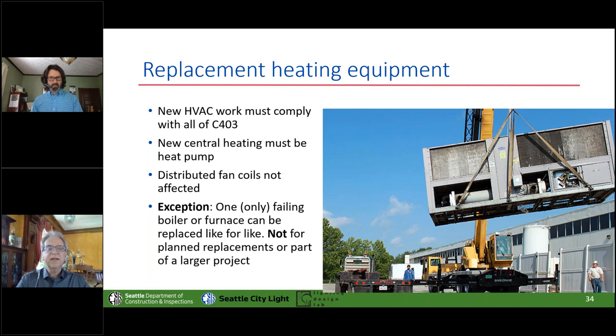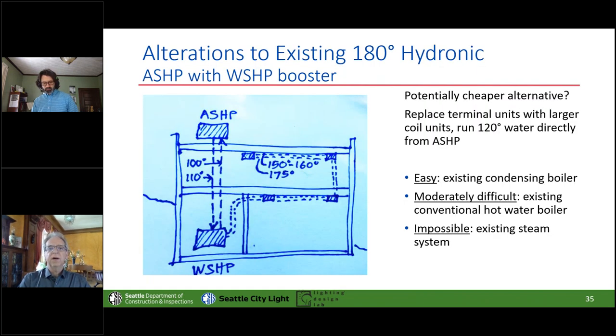And we did, in fact, make an exception to my rule that new stuff all has to meet code. It says if there's one piece of equipment, and only one, and it's failing right now, you can replace it like for like. Now, the question then comes up, as it did recently with one of our local colleges: we have a hydronic system that's running at 180 degrees sometimes, on a cold day. How do we convert that to a heat pump? How is it even possible? So take it away, Ben.